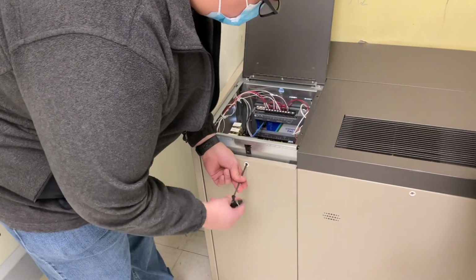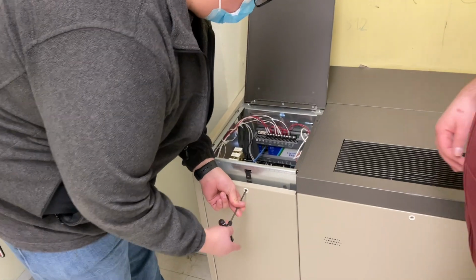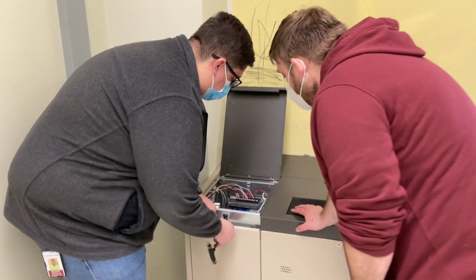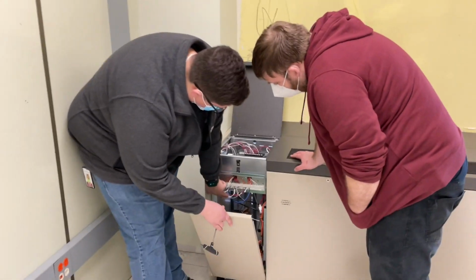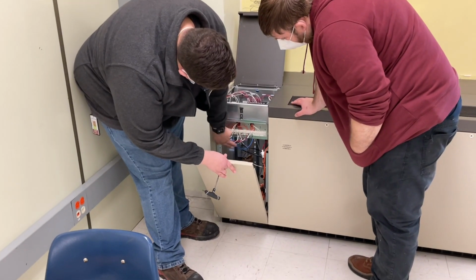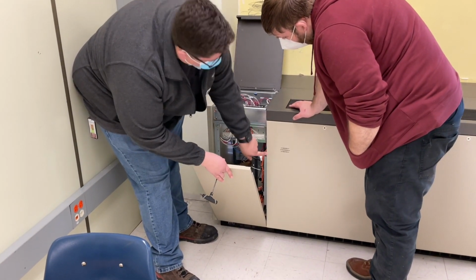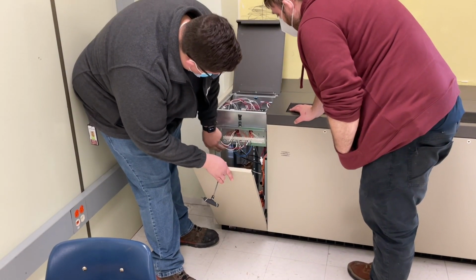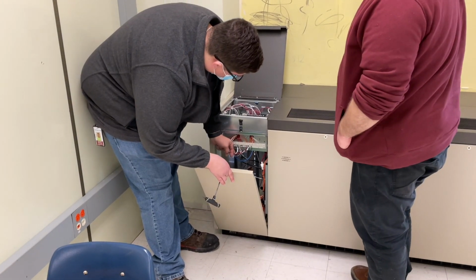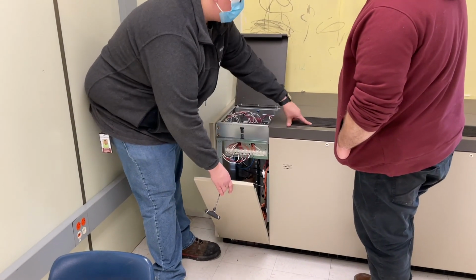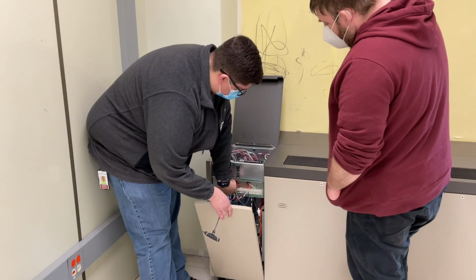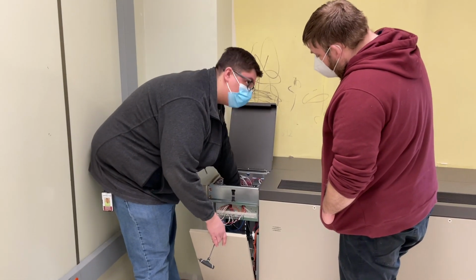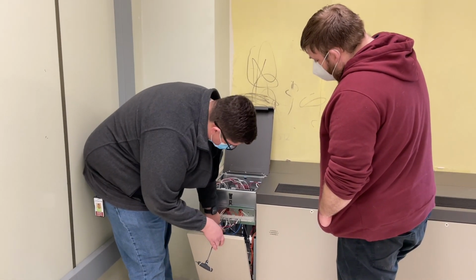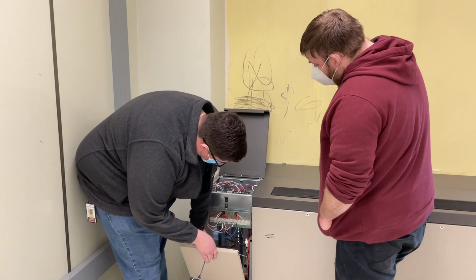And then on this side, everything that we're controlling comes back to a terminal strip in here. Then these go out into the unit and they have their own control board on the other side. So like this DAT here, the discharge air temperature comes back to here, and then this goes back to us. That's where we're reading it at. All the commands, things like that.